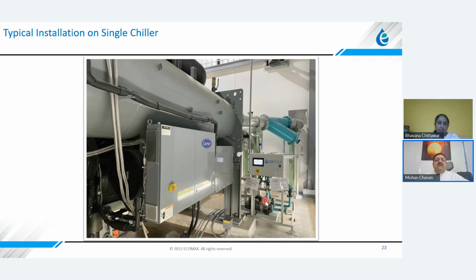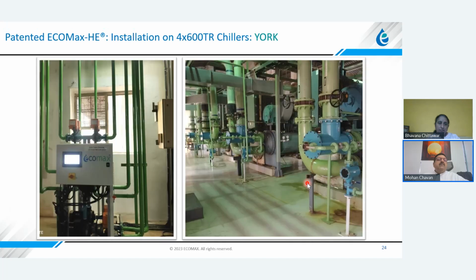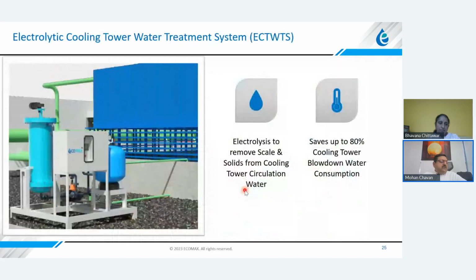These are some of the typical installations wherein you will find there is a skid, there is a ball trap, and there are ball collectors. It's a very simple installation. It's a simple technology, but very effective. Here you will see that one skid is able to manage multiple condensers. Individual chillers will have their own ball trap and ball collector, so that the ball set is individually separate for each chiller. So that's to save on the costs, capex.